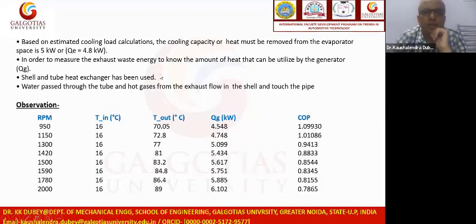So these are the considerations for the cooling space from the thermal calculation. The load is about 5 kilowatt or 4.8 kilowatt. By using the thermal analysis, I'm not showing all the detail here, I'm just showing the output of this analysis. So we can see that as per the RPM, we are fixing the T input temperature from the generator side, and the outside temperature is changing. The Q generator, meaning the generator energy, also changes, and the COP is also changing. The coefficient of performance basically depends on the cooling effect divided by the Q generator, because in this system the Q generator is the input energy and our output is the cooling effect.